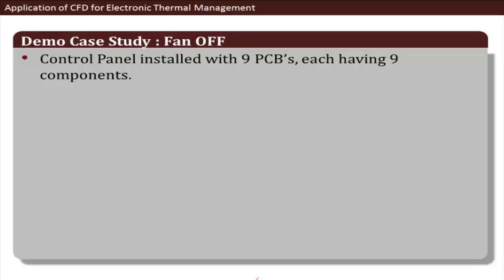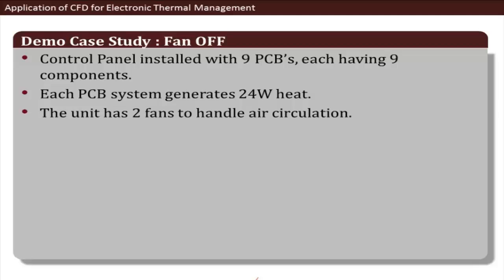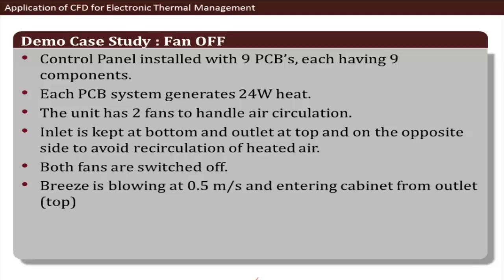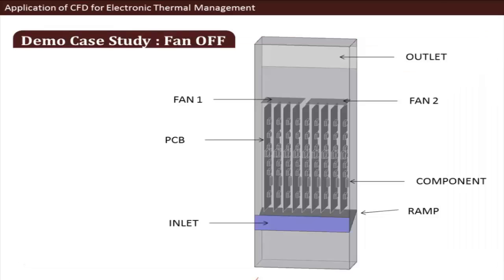The model is a control panel with nine PCBs, each having nine components. Each PCB generates 24 watts of heat. The unit has two fans, but they are switched off to simulate the worst case. The inlet is at the bottom and the outlet at the top to avoid recirculation. A natural air breeze of 0.5 m/s enters from the outlet side. The domain shows the nine PCBs with components, two fans, and a ramp used to redirect air through the PCB racks.